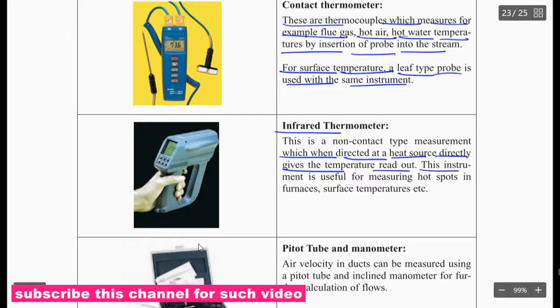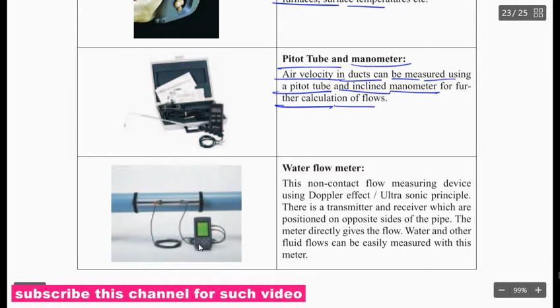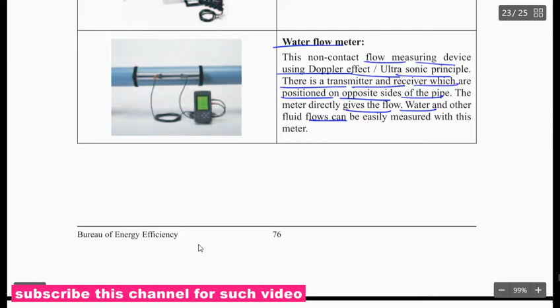Pitot tube and manometer. The air velocity in a duct can be measured using the pitot tube and inclined manometer for further calculation of flows. Water flow meters. This is a non-contact flow measuring device using the Doppler effect and ultrasonic principle. There is a transmitter and receiver which are positioned on opposite sides of the pipe, and the meter directly gives the flow. Water and other fluid flow can be easily measured with this meter.